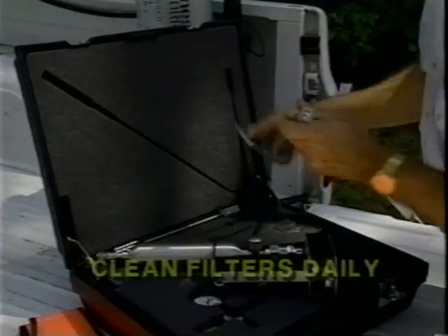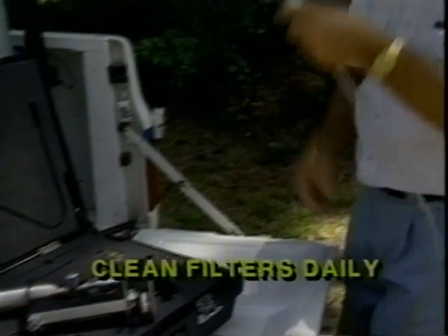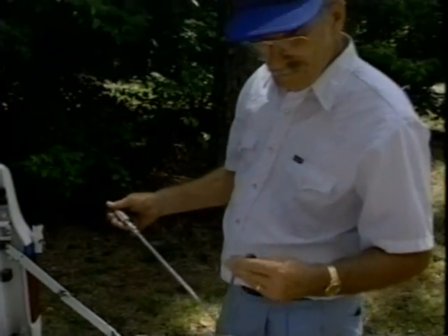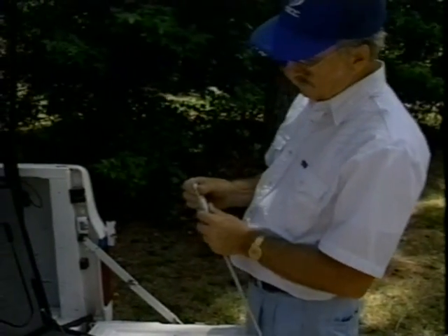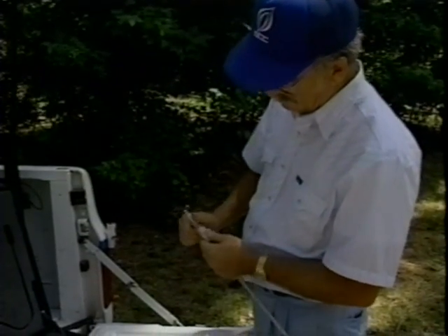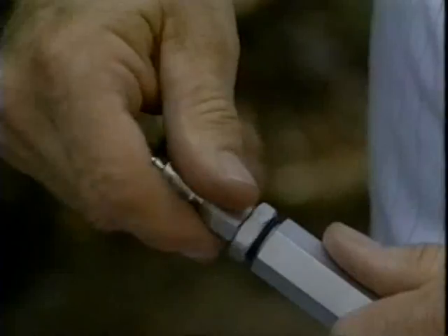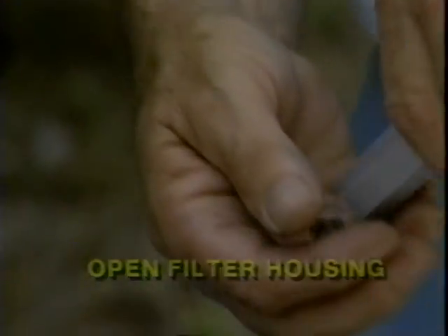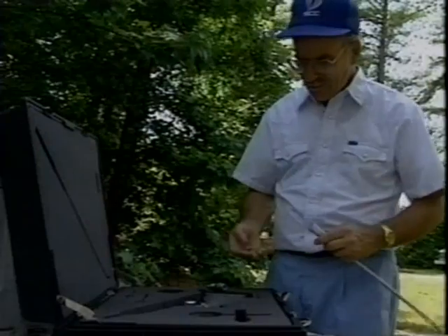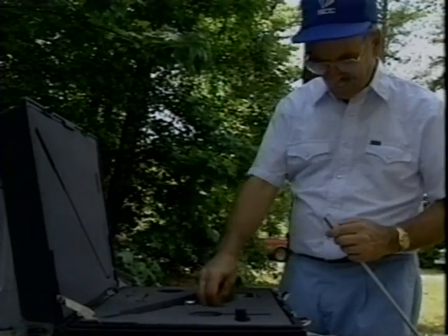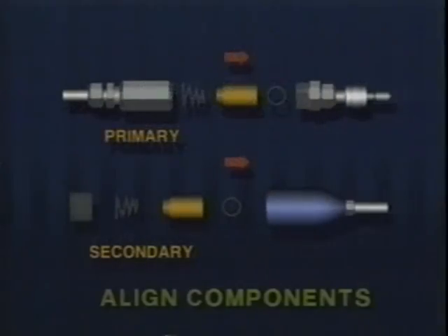These filters should be changed or cleaned daily. They are made of bronze and designed for reuse. They can be washed with soap and water, but must be dried thoroughly before reuse. To replace the upper filter, simply open the housing and take out the filter. Remember, be very careful not to lose any parts, particularly the filter gaskets and O-ring. When installing a new or cleaned filter, be sure that the components are aligned properly.